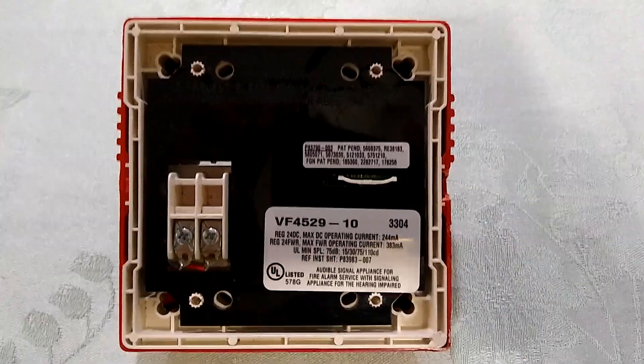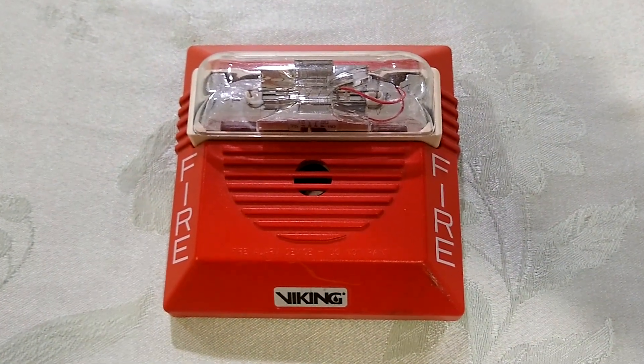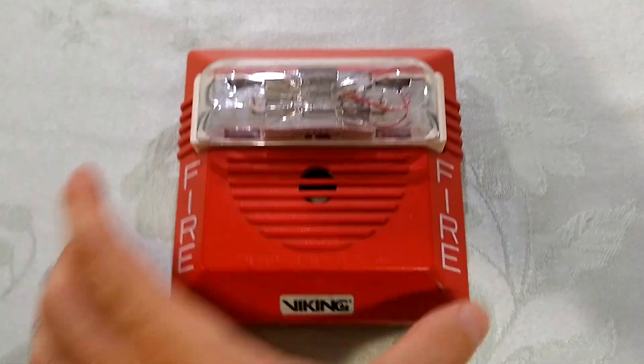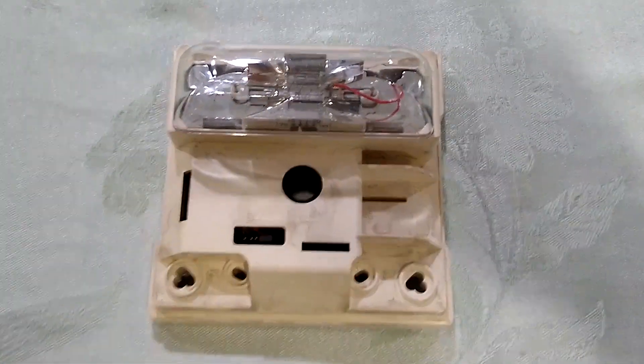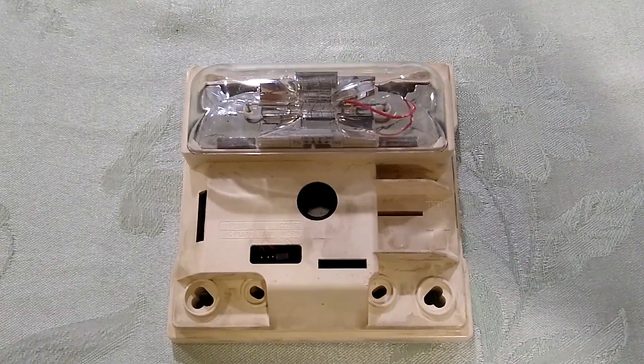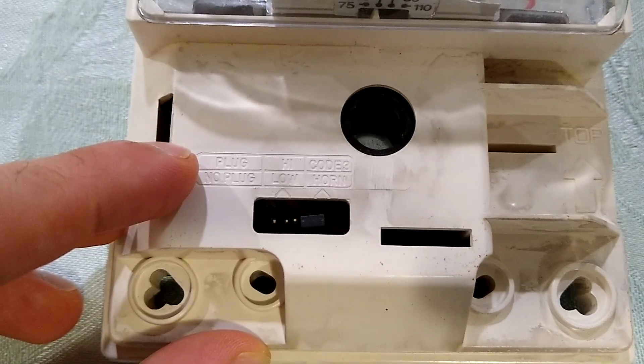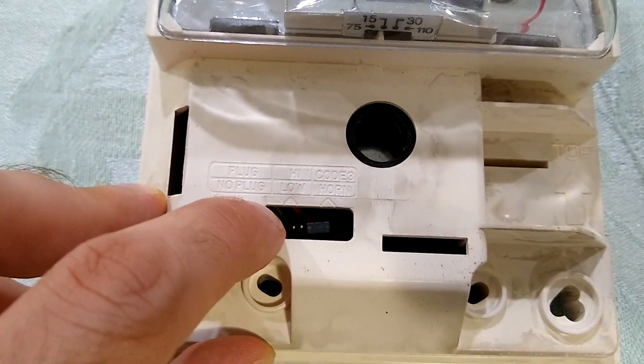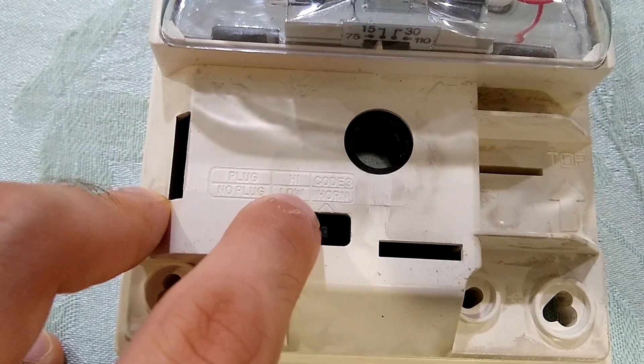Now this is my Viking VF4529-10, but really it's a Wheelock NS24MCW that's just been rebranded by Viking. Now this NS series is a similar design to the Simplex TrueAlert, with this removable cover plate and then this actual horn strobe that you screw onto the back box. The horn settings could be adjusted by adding or removing the jumper plugs in here. There's a little chart here that shows you to put in the plug for high and remove it for low volume, and put it in for code 3 and remove it for just steady horn.